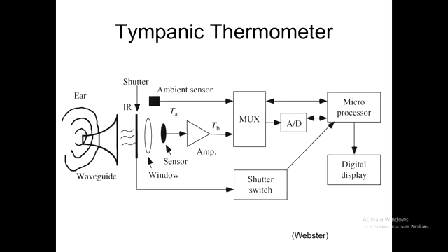Basically, it's a Boltzmann style black body detector, amplified up, and it needs to be normalised against or calibrated against an ambient sensor. So there's another sensor put in. It might be one of those other ones.